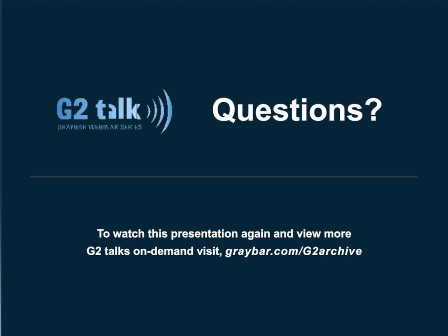All right, this one is for John. Somebody wants to understand if they heard correctly, the auto GFI is a requirement by July 1st, but existing are grandfathered? That is correct. You don't have to replace anything that's already installed. You can continue to install the pre-June 29th product, and Graybar can continue to sell the pre-June 29th product. The only ramification is Hubbell, Leviton, Cooper, Pass and Seymour. None of the manufacturers can manufacture the product without the self-testing microchip in it after June 29th.